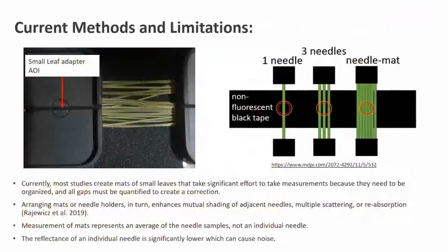And the benefit of our pine needle adapter is you can target an individual leaf as opposed to a bundle. Arranging pine needles in bundles has a lot of different limitations. It increases mutual shading of adjacent leaves, multiple scattering, and reabsorption by the pine needles. So the best practice for scanning a pine needle would be to measure one at a time. You can be as targeted as you want with our instruments. This pine needle adapter can be used for the surface probe as well. It fits the same way. The pine needle adapter is the most targeted way you could take a leaf reflectance measurement.